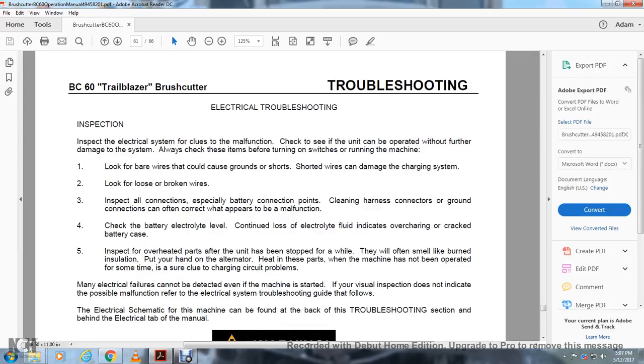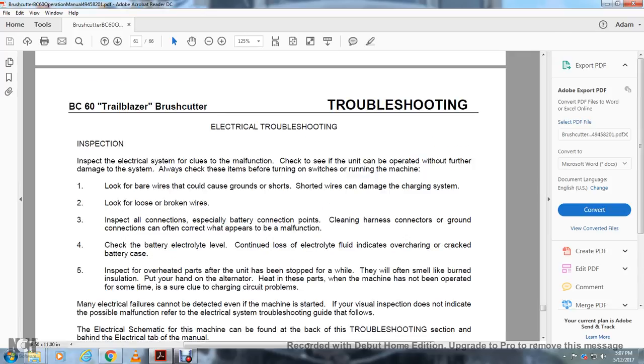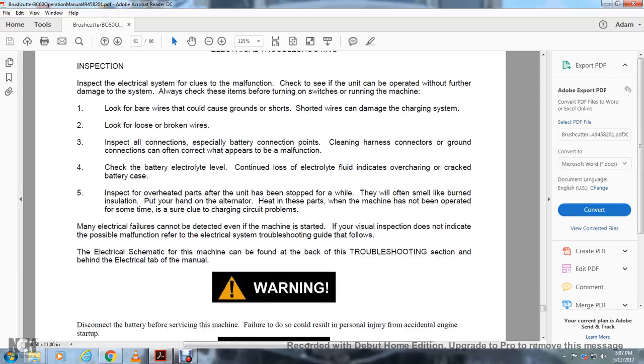Check the battery electrolyte level. Continued loss of electrolyte fluid indicates overcharging or a cracked battery case. Inspect for overheated parts on a unit that has been stopped for a while; they will often smell like burned insulation. Put your hand on the alternator to feel the heat in this part when the machine has not been operated for some time. It is a sure clue to a charging circuit problem. Many electrical failures cannot be detected even if the machine is started. If the visual inspection does not indicate the possible cause, refer to the electrical system troubleshooting guide that follows.